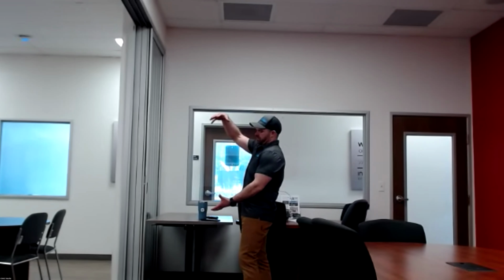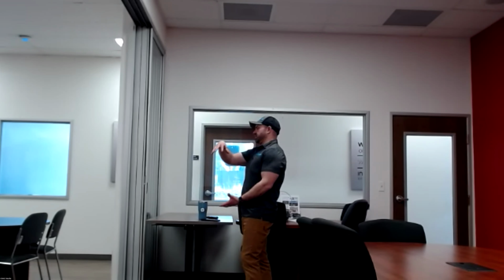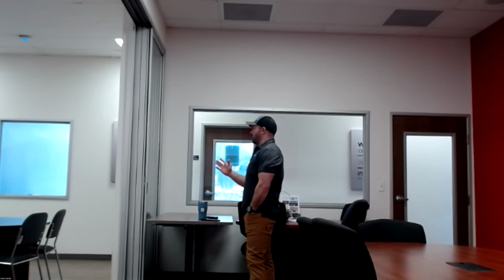What I really like about these is that they're very energy efficient also. They're also super low maintenance as far as water heaters go, because there's no heating element or burner assembly like on an electric or gas water heater for it to burn out. It's just a radiator that sits in there, which generally lasts a really long time. It's not uncommon to see 20, 25 years out of a sidearm water heater.